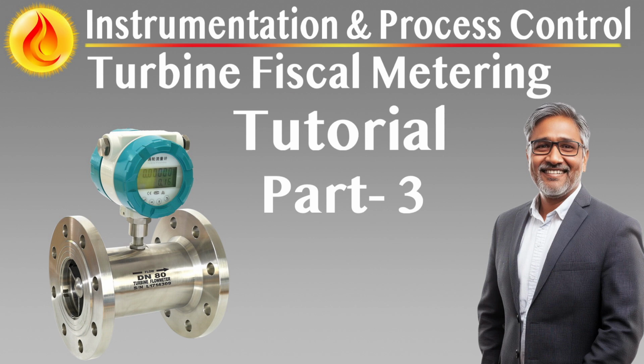Redundant pressure monitoring for real-time compensation and calibration integrity. Each metering stream must include both electronic pressure transmitters and mechanical pressure gauges for monitoring operating conditions and supporting dynamic flow compensation. The electronic transmitters must be of the smart type with 4 to 20 milliamps analog output and optionally with digital communication capabilities for diagnostics and configuration. They must meet high precision tolerance classes and maintain calibration stability over extended periods.